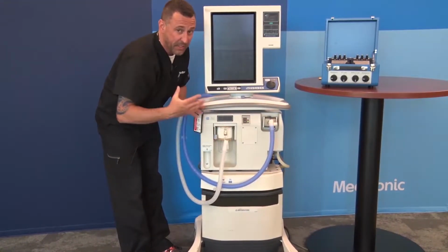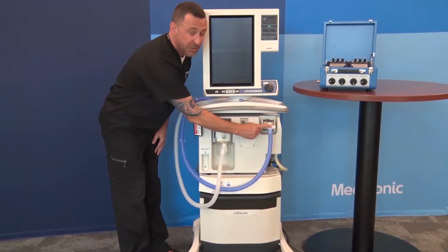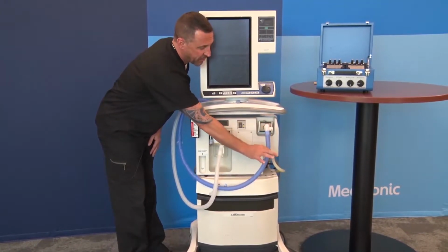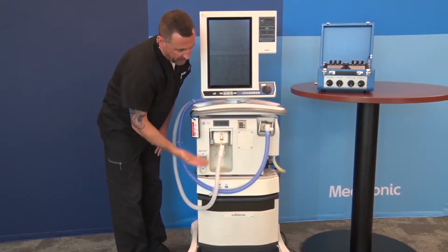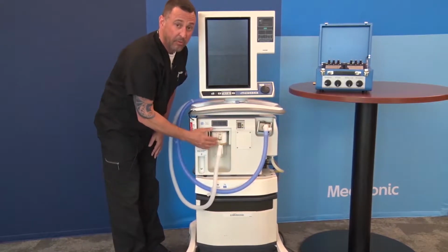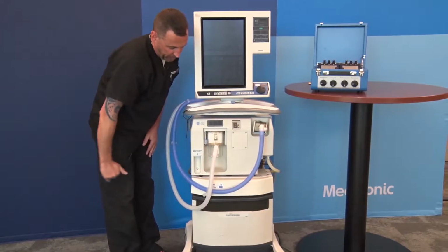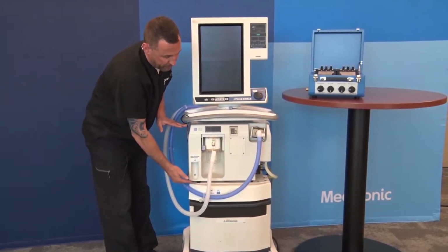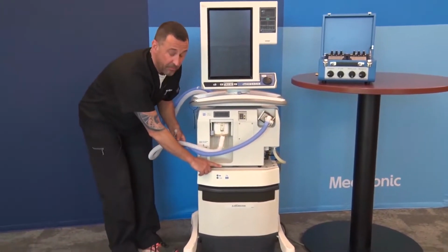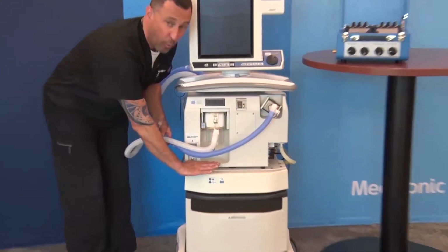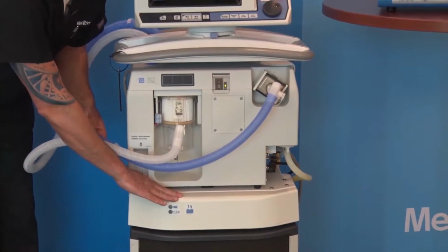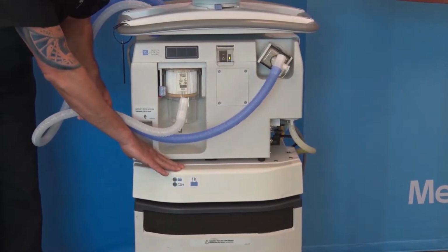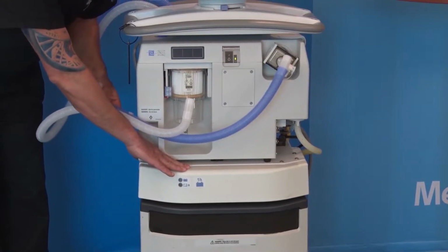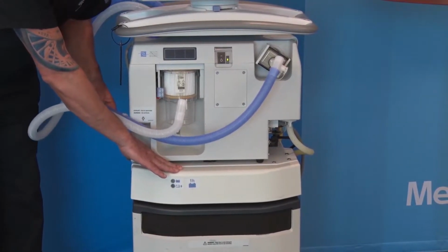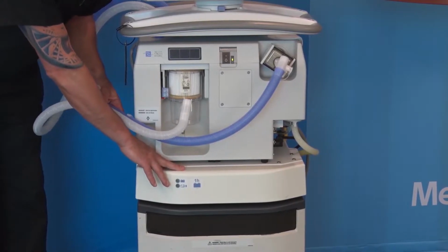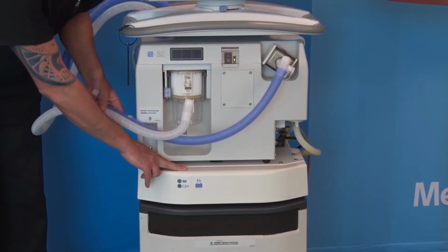That is where gas is mixed and ultimately delivered to the patient on the inspiratory side through an inspiratory filter and obviously the inspiratory limb of a circuit, and the patient would exhale back through the expiratory limb, through the expiratory filter, and out through the ventilator it goes. So that's your breath delivery unit. The ventilator comes configured in a standard configuration with either a 1 or a 4-hour battery. Remember this, the 840 ventilator is a little older, so these are sealed lead acid batteries. They are not hot swappable or lithium ion, so these do need to be plugged in at all times to keep that battery at a full charge for you.